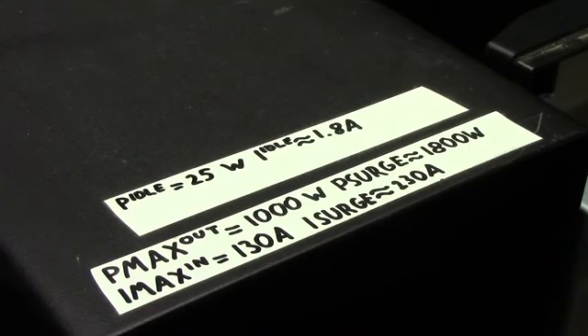As for the actual performance of the thing, well, as the two giant fans cut out on the side should bear witness to, isn't too great. At idle it will use about 25 watts just sitting and chugging the inverter along and running the fans, and the efficiency levels you'd get on the load are, on the very low end, something like 40 to 60%, and when you're approaching the top output power of about 1000 watts, it will just about get up to 80% if the weather's alright and the birds are chirping outside. But for the most part, on the medium load, it'll sit at somewhere around 75% or thereabout. So it's not a particularly solar-friendly device, since it's got a high idle consumption and a rather disappointing efficiency.